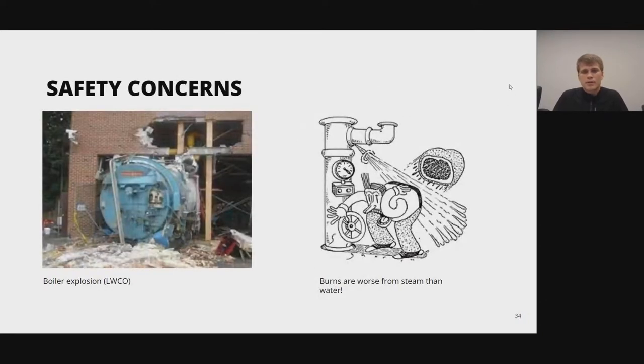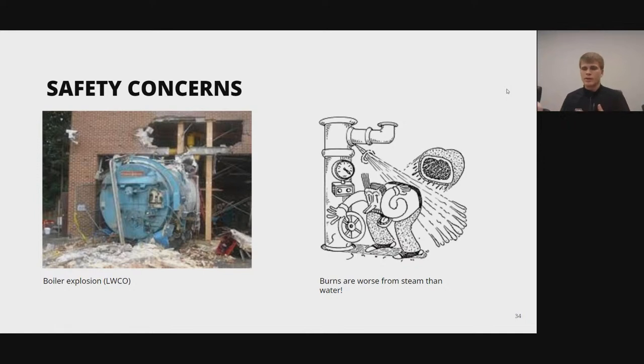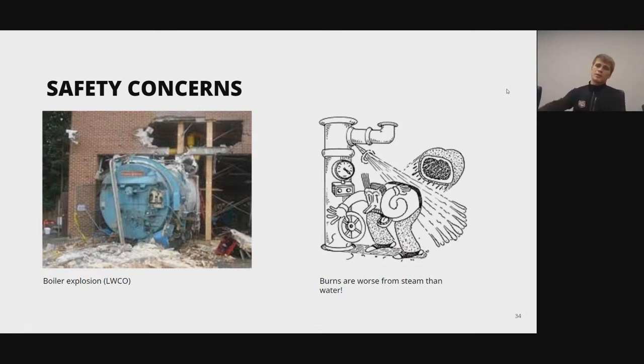Here on the left is a picture of a boiler explosion caused by a failure of a low water cutoff. All the water inside the boiler had boiled off and the boiler began to overheat. Once feed water was injected, it caused a massive amount of flash steam because the boiler was superheated — the water flashed off, creating a massive pressure surge, and it blew up.